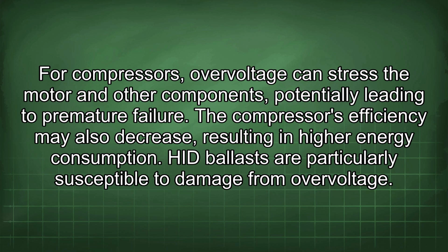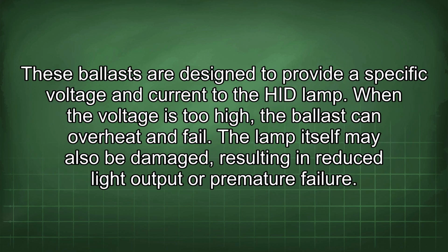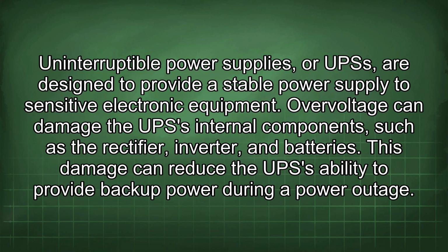HID ballasts are particularly susceptible to damage from overvoltage. These ballasts are designed to provide a specific voltage and current to the HID lamp. When the voltage is too high, the ballast can overheat and fail. The lamp itself may also be damaged, resulting in reduced light output or premature failure. Uninterruptible power supplies, or UPSs, are designed to provide a stable power supply to sensitive electronic equipment. Overvoltage can damage the UPS internal components, such as the rectifier, inverter, and batteries. This damage can reduce the UPS's ability to provide backup power during a power outage.